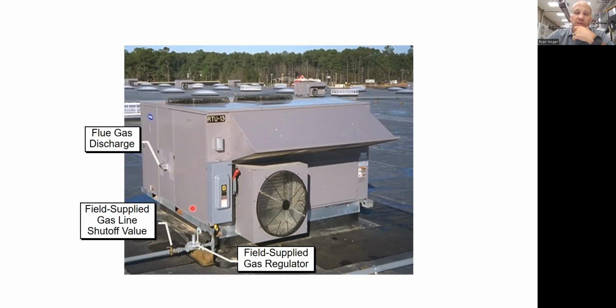So at a lot of places like your house, for example, you've got a furnace or a boiler, and there's a flue coming off of that, right, where all the products of combustion can leave the home, and that flue goes all the way up to the second story of your house and then discharges out. We don't need that ductwork in this case because we're already outside. So the flue is literally like 6 inches long. It just has to push it a little bit away from the unit to get a little throw, and that's it. It doesn't involve anything else. So when it's running heat, that guy is discharging flue gases right here on the side.